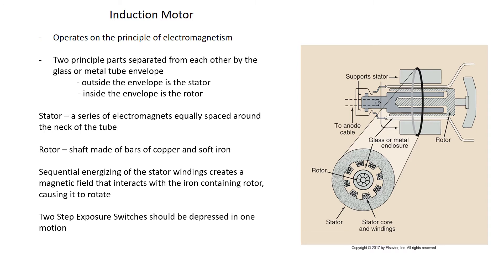Two-step exposure switches should be depressed in one motion. There is a common clinical habit of activating the rotor first, holding it down, giving breathing instructions, then pressing all the way down for the exposure — however, any textbook will tell you not to do that. You should push all the way down in one motion; the electrons won't reach the anode until the rotor gets to the correct speed, which happens very quickly.